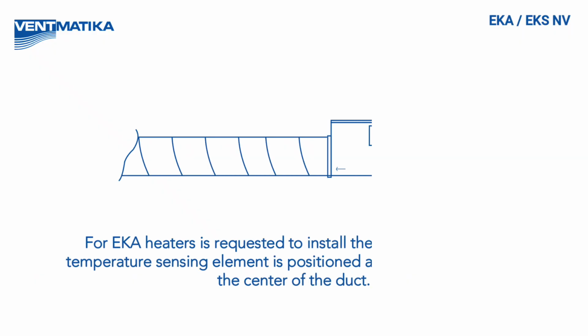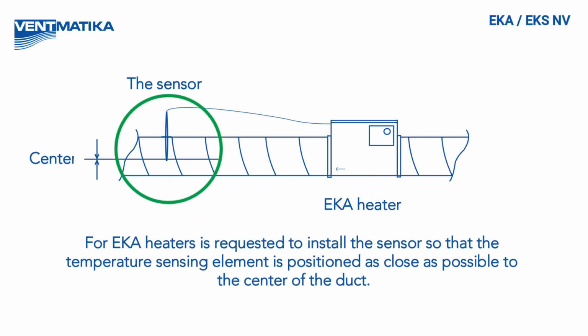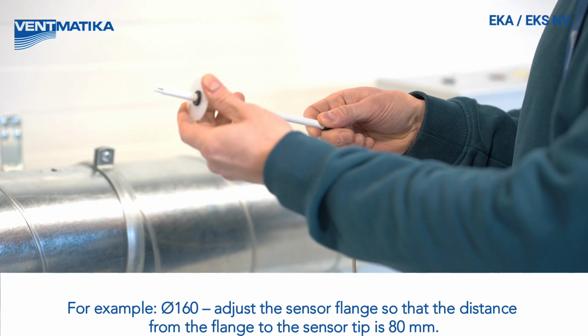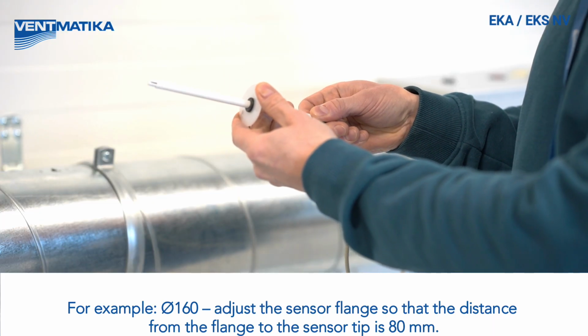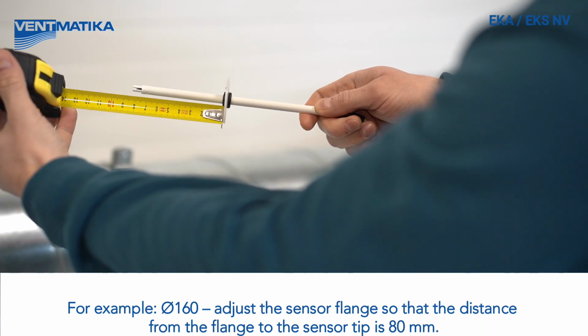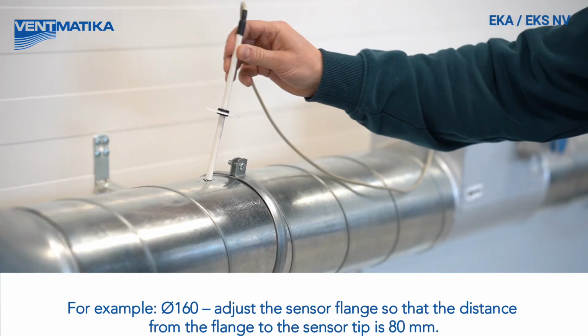For EKA heaters, it is requested to install the sensor so that the temperature sensing element is positioned as close as possible to the center of the duct. For example, diameter 160. Adjust the sensor flange so that the distance from the flange to the sensor tip is 80 millimeters.